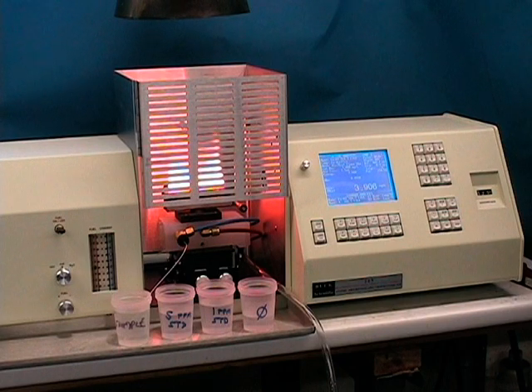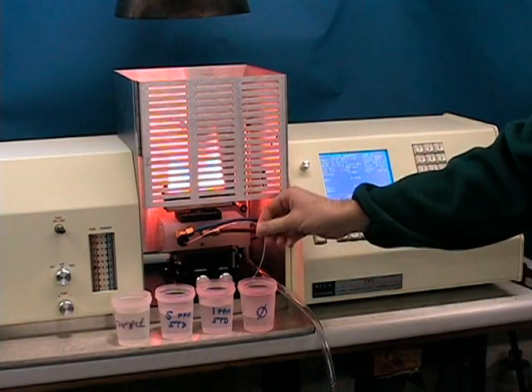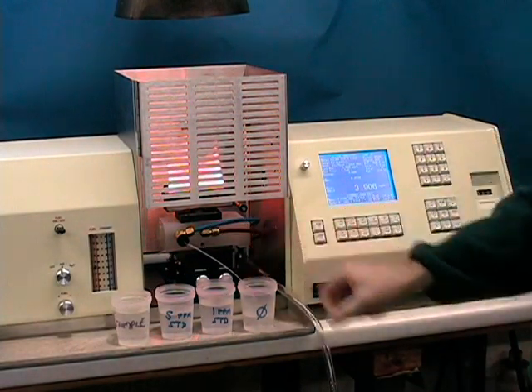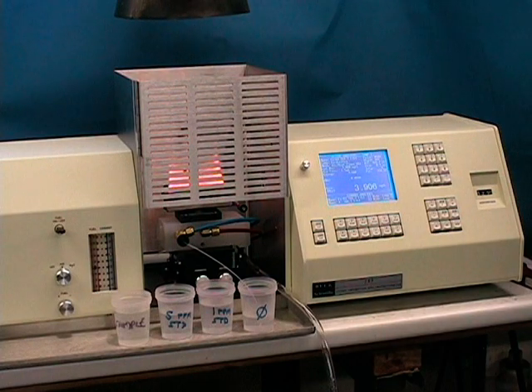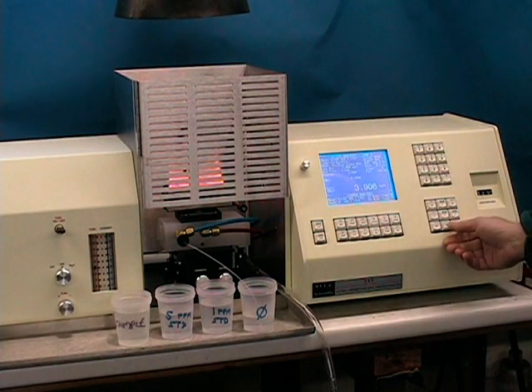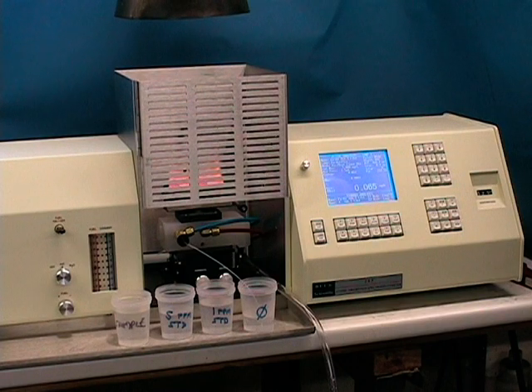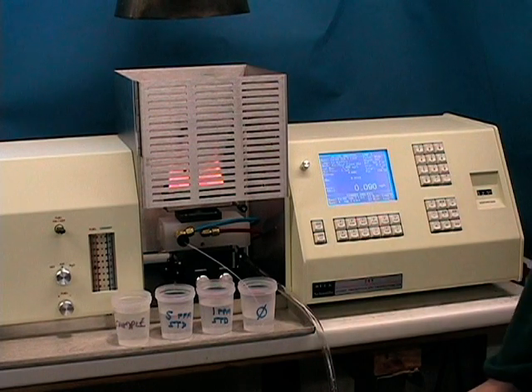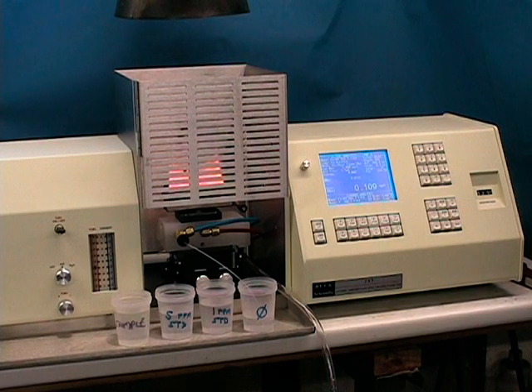When you're ready to run a fresh sample, it is recommended you go back into your blank solution to flush out any high dissolved solids and press the escape key to free up the display as you watch your blank return to 0. You may continue with your analyses, checking your standards every 10 sample readings approximately to verify the accuracy of your calibration curve.